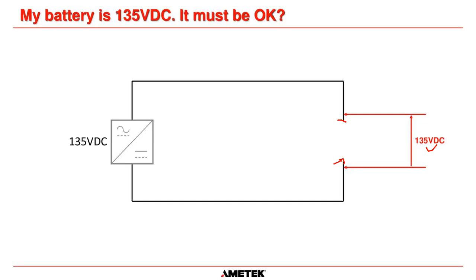So if we have one battery connected to a charger across positive and negative, we'll read 135 volts DC. But if you remove that battery and still look at the termination points, you'll still measure 135 volts DC. So whether your battery is there or not, it's the charger voltage you're reading, not the battery voltage.